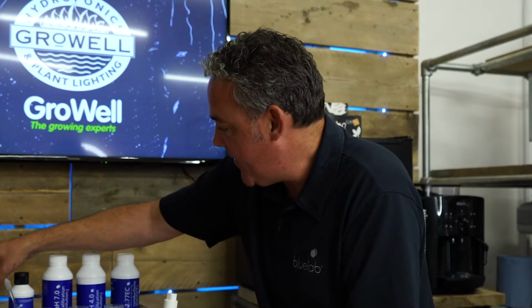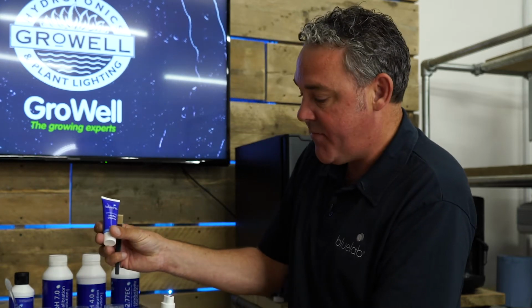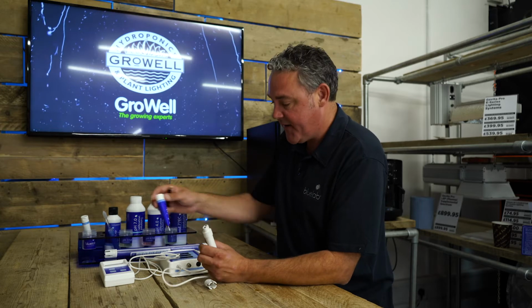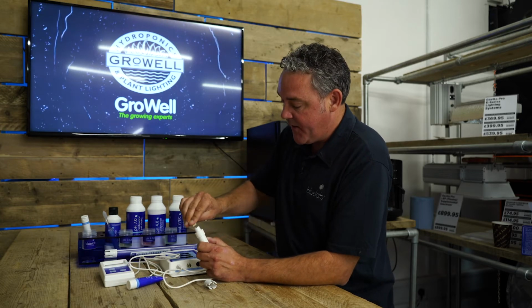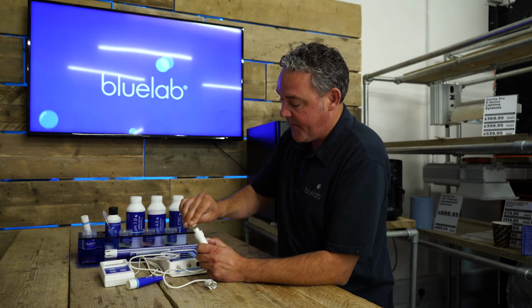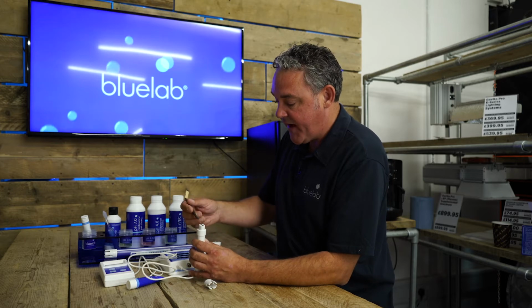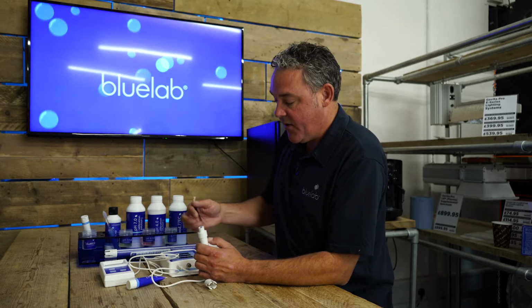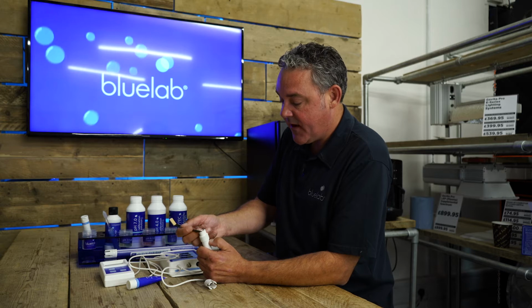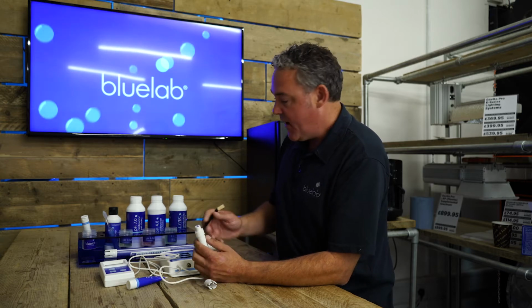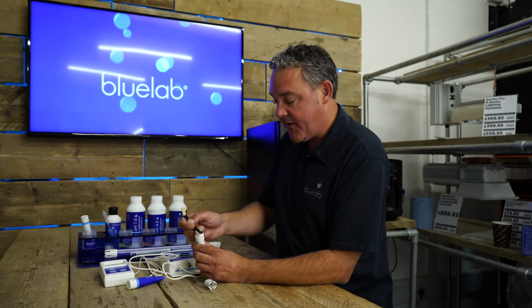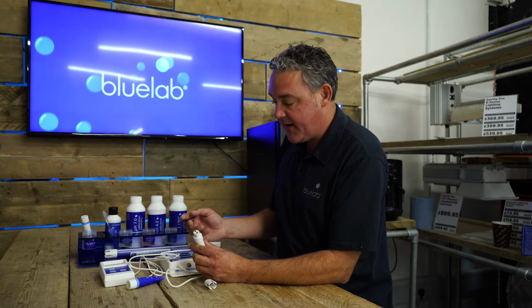And to clean it, you just use our conductivity probe cleaner. This is an abrasive paste, and you just put it on there, you give it a clean with the chamois, and what you'll start to see is the paste will turn from white to black, and all you're doing is taking off the top layer of carbon of these sensors. And Bluelab is unique in the fact that we have a flat sensor. It makes it incredibly easy to clean.